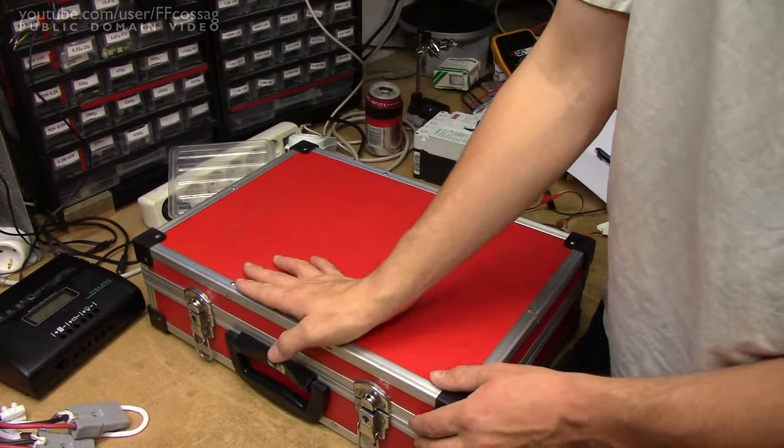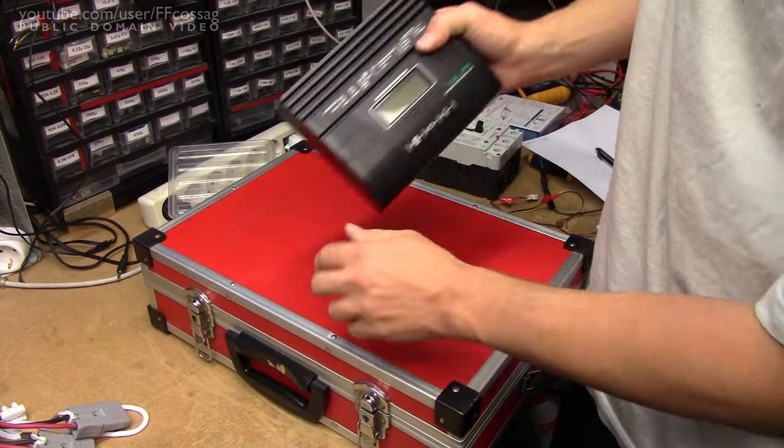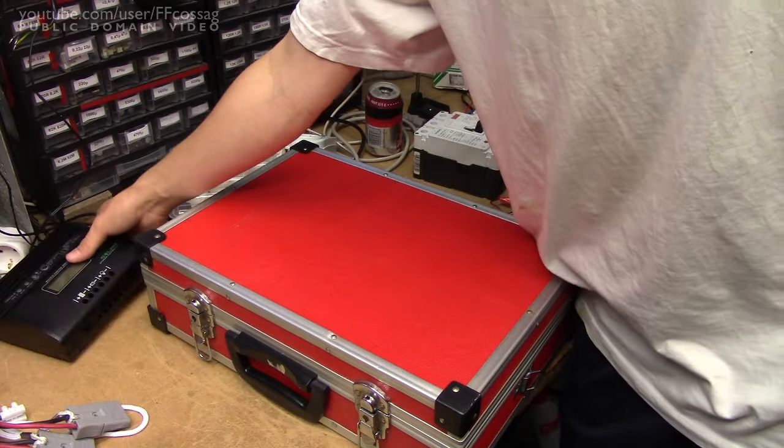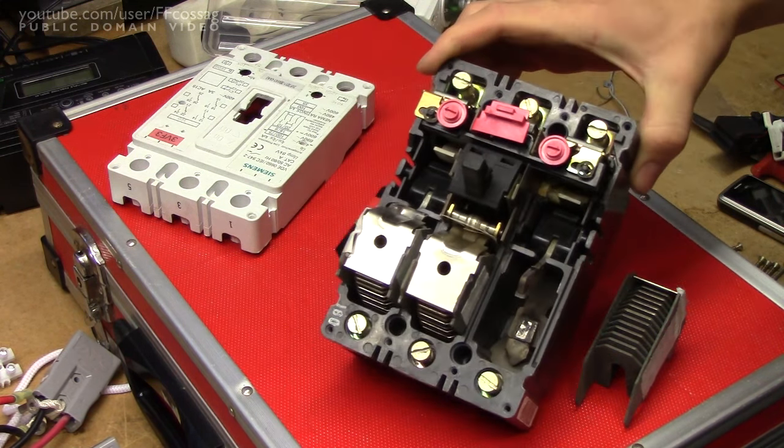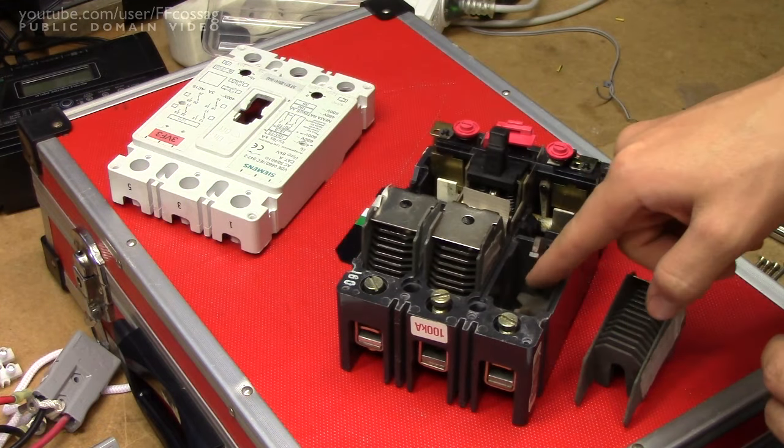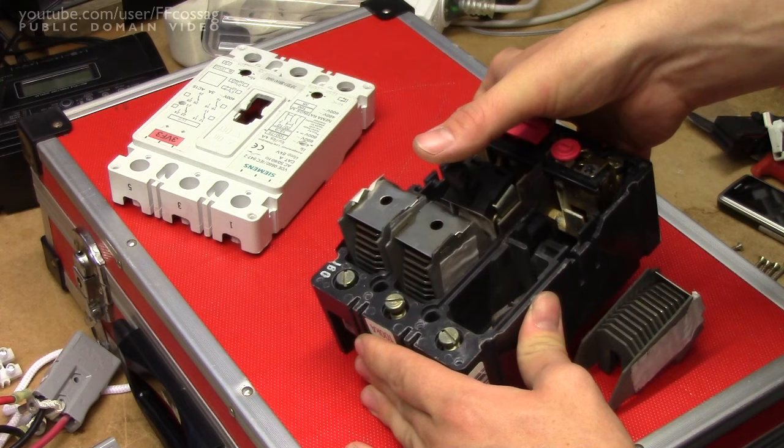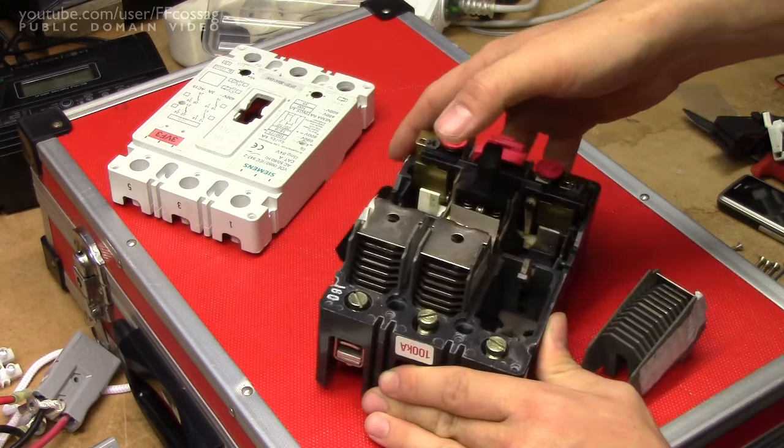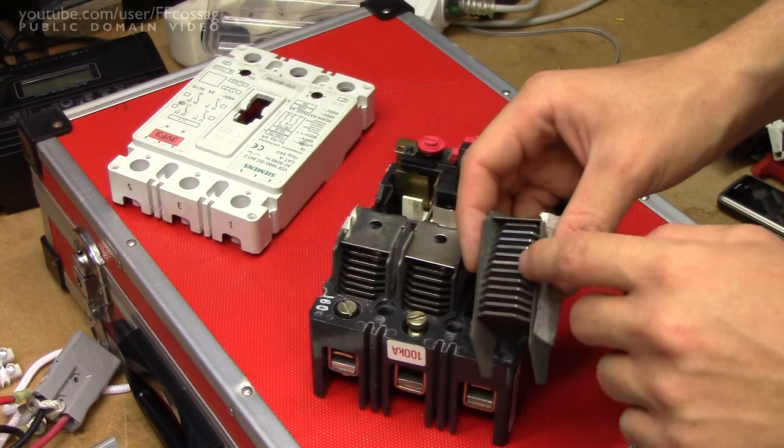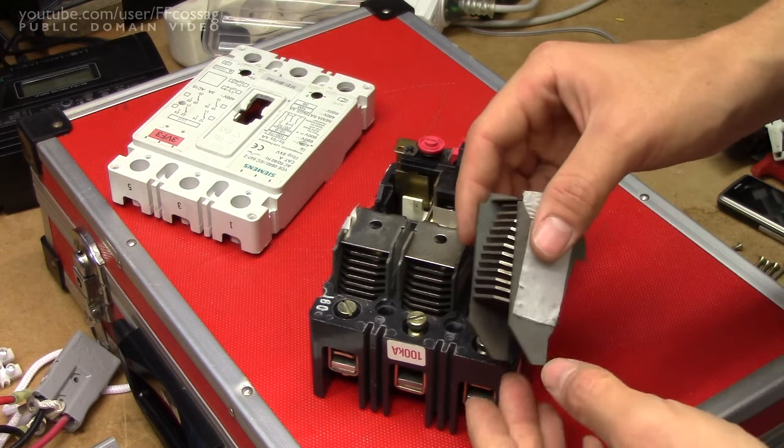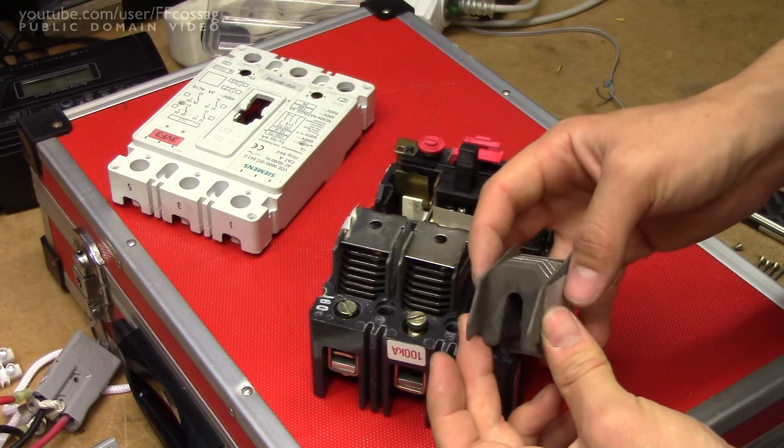Now I'm going to cut a big hole in this panel because this guy does not like to be in enclosed spaces and I don't need it to be particularly well protected anyway. And if you're curious to see what goes on inside of a 160 amp AC or DC resettable fuse, well here you go. That's some quite considerable isolation going on. I'm not entirely certain what this assembly is intended to achieve but it seems to be collecting grime that comes flying off when that giant arc is made and perhaps it's acting as some kind of flame suppressor.